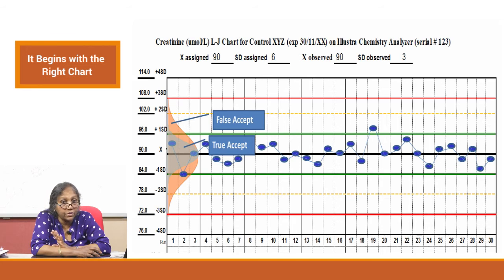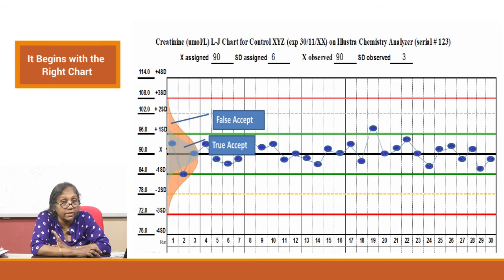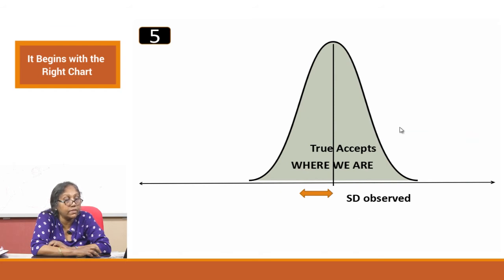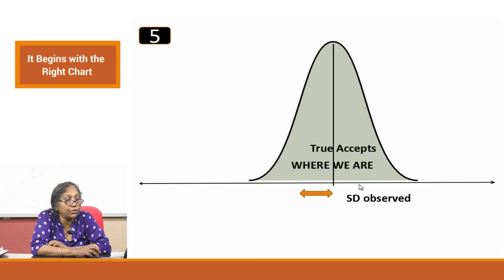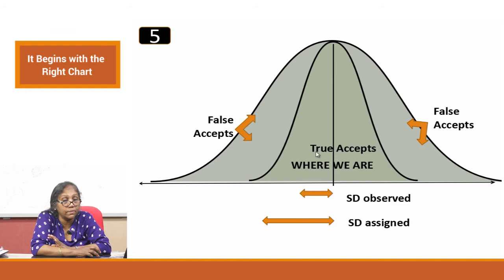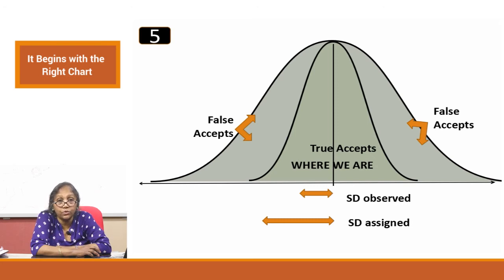Can you have 100 percent of your data falling between plus and minus 1 SD? That region can only contain 68 percent. So if everything sits there, that is a wrong graph — it is not a Gaussian. Only a small area represents true accepts; beyond that you are falsely accepting readings because you have not defined your SD correctly. You are assigning it much larger than observed, so you are accepting many false values that should have been rejected.